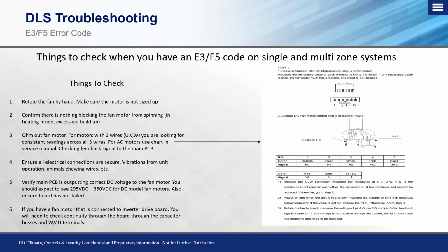why you're coding out. Now, if you're dealing with the 5-wire connections on there, you want to first power the unit on. When the unit is in standby, which is when you first power it on, you want to measure the voltage of pin 4 and 5. So we look at 4 being the pink wire, 5 being the black wire, in that feedback signal connector or the Molex pin. Okay, if the value is not 5 volts DC, or excuse me, AC with the AC fan motor, change the main PCB.